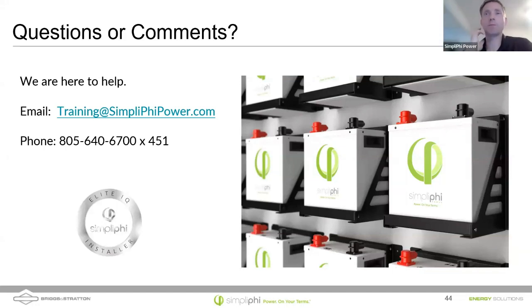The batteries themselves, if they're in a resting state of charge, shouldn't be at 56 volts. The charge controller itself will be at 56 volts during a charging cycle. But as soon as the charging cycle ends, the voltage of the battery should drop down to about 53.5 volts. So a fully charged battery, when the charge controller is not running, will be at about 53.5 volts. It depends a little on the temperature.